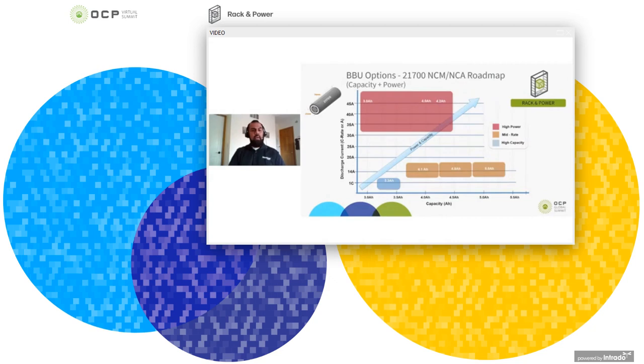If you need higher than 3 amp hours or 35 amps current capability, then we need to start looking at the 21700 cells. This is the new class of cells that started several years ago, made famous by Tesla. These cells are used in the Tesla Model 3. With these cells, we can get close to 50 amp output from one cell and around 4 amp hours of capacity. The biggest recommendation we give to customers is to design the BBU to be able to handle both the 21700 and 18650 cell geometry. This gives us the ability to switch between them and makes it future-proof.